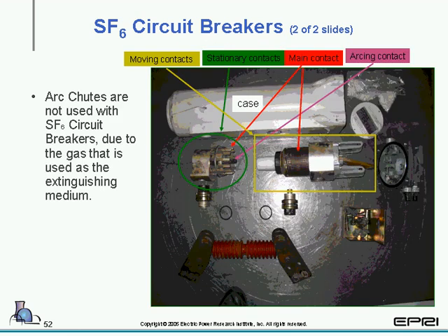We have an example of an actual SF6 circuit breaker bottle disassembled. You see the moving contact structure, you see the stationary contacts, you see the main contacts, and you see the arcing contacts. And you only see one arcing contact shown by the purple. If you look at the moving contact structure, inside this white tube is the actual arcing contact, and that's where the gas is being forced past that tip.